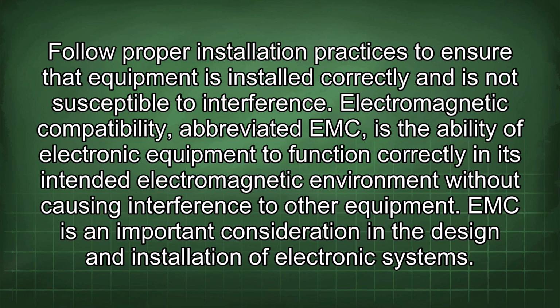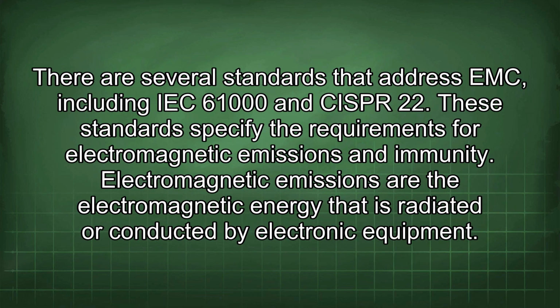Electromagnetic compatibility, abbreviated EMC, is the ability of electronic equipment to function correctly in its intended electromagnetic environment without causing interference to other equipment. EMC is an important consideration in the design and installation of electronic systems. There are several standards that address EMC, including IEC 61000 and CISPR 22. These standards specify the requirements for electromagnetic emissions and immunity.